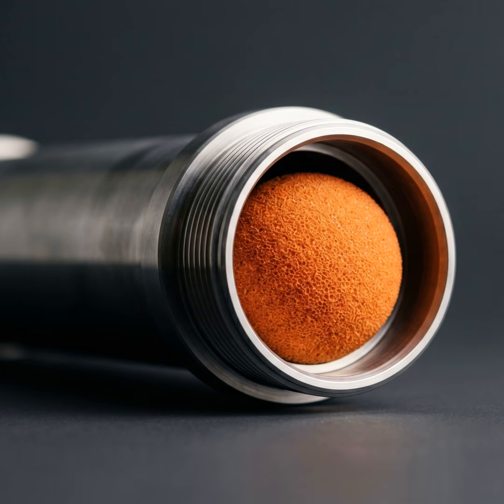Exactly. So instead of running the fan at 100% and failing miserably, it calculates the optimal reduced fan speed to hit that realistic physical limit, and it stops there. It refuses to waste energy fighting the impossible. Exactly. Let's talk about the energy savings here, because earlier you mentioned the math behind it, and I want to make sure I understand it. You mentioned the affinity laws in relation to fans. Walk me through that math.